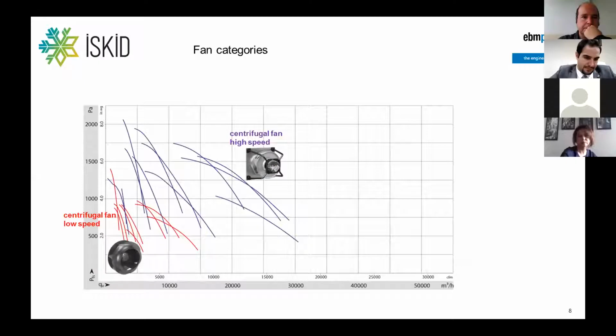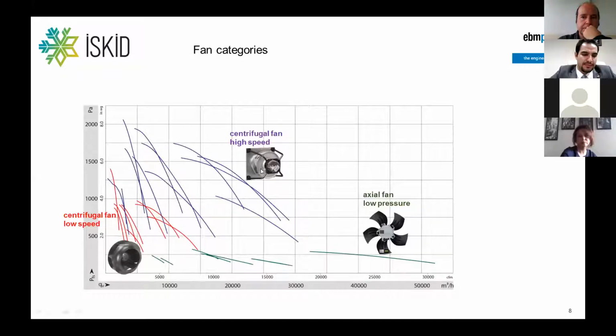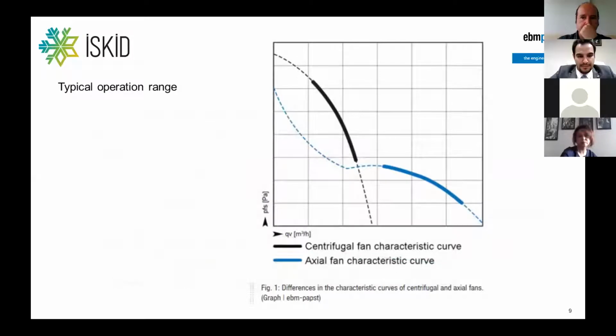Fan categories, as you know, are centrifugal fans for lower speed, higher speed, and there are axial fans. In most cases, nowadays, centrifugal fans are used. Axial fans tend to be more on the low pressure side, but there are also some companies coming up presenting axial flow fans in air handling units. The characteristic of a centrifugal fan in general is, as mentioned, a little bit towards higher pressure, and the axial fan to the lower pressure. This is the overall explanation of such kinds of fans.